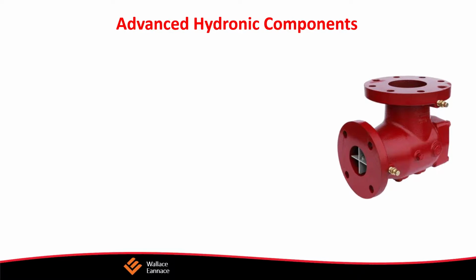With the primary secondary headers, here you can see an application where they use them. So what you have is this primary secondary piping, with closely spaced T's. The boiler pump is flowing in this direction, and the secondary circuit is going to the radiation in this direction. So you have one path this way, one path this way. Instead, we can do the same thing. We can eliminate the need for this air elimination device by putting this in here and making sure that we have it sized and set the primary secondary circuit properly. In addition, we have a blowdown here for getting rid of any sediment in the system, and an air vent on the top too. So these are devices that we highly recommend.